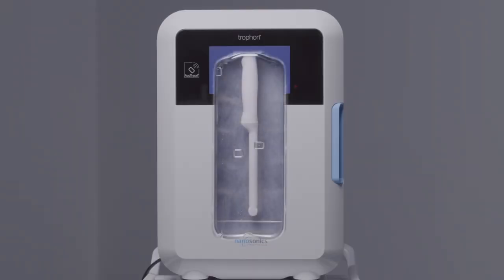Trophon does high-level disinfection of ultrasound probes. An ultrasound probe is obviously a reusable medical device in most cases. They're quite expensive, and so we have to make sure that the microorganisms from the first patient are not transmitted to the second patient. That involves cleaning and high-level disinfecting the probe. The way that Trophon works is it uses hydrogen peroxide. It nebulizes this into a fine mist, and that fine mist coats the probe and disinfects it within the chamber.